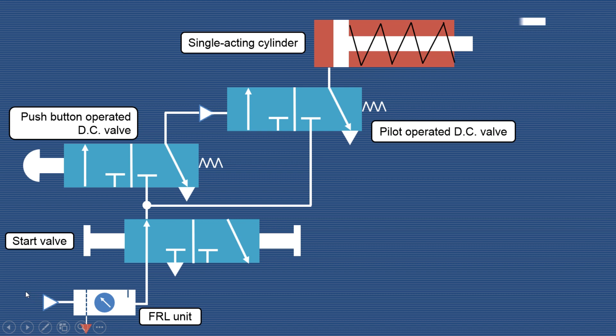Let us trace the circuit once again. Air from the compressor enters the FRL unit. The start valve is in the left envelope mode, and the push button operated direction control valve, which is a normally closed (NC) valve, is in the right envelope — the block position. Air from this line enters the right envelope of the pilot operated DC valve, which is also in the block position since the push button has not been operated. Therefore air is not admitted into the single acting cylinder, and the spring force causes retraction of the piston. Air from that side exhausts to atmosphere.